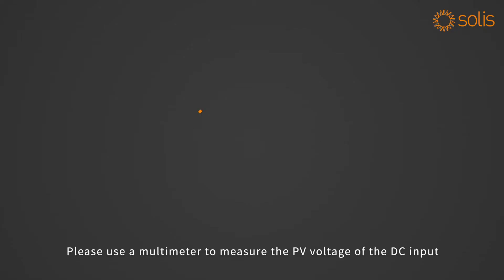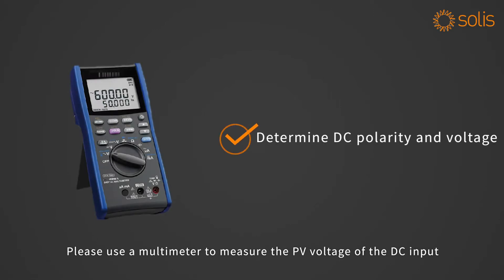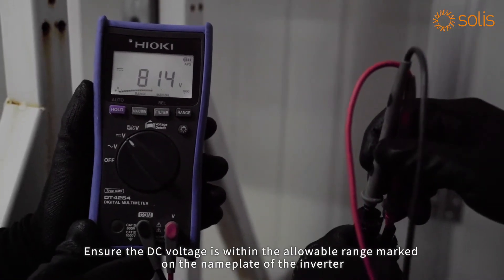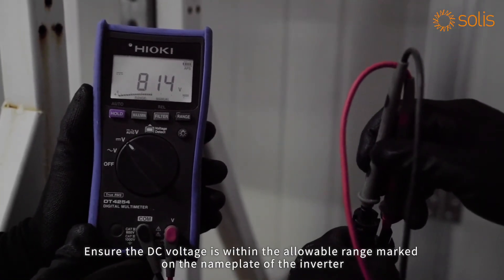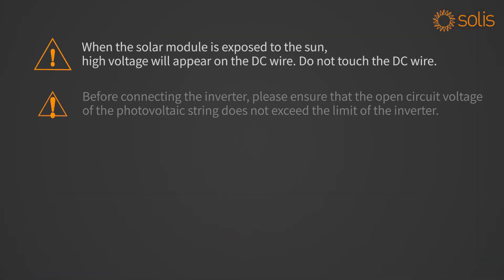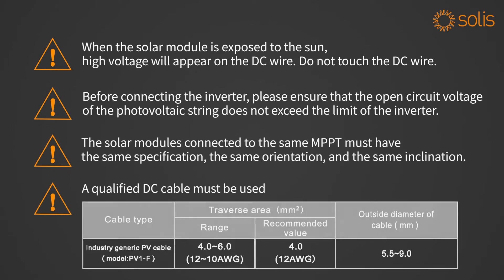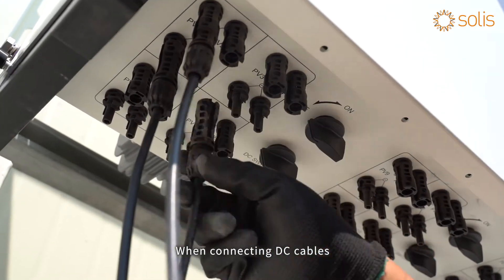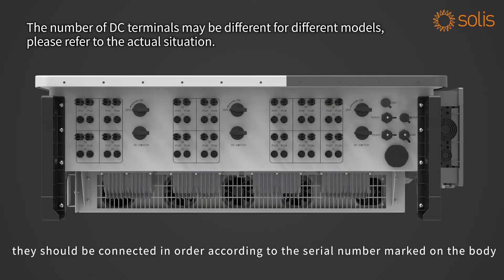DC side connection: please use a multimeter to measure the PV voltage of the DC input and distinguish the positive and negative poles. Ensure the DC voltage is within the allowable range marked on the nameplate of the inverter. Please refer to Solis demonstration video for making the DC connection cable.